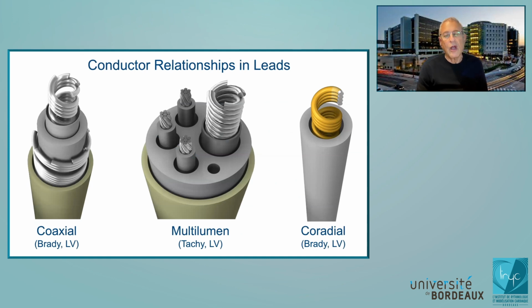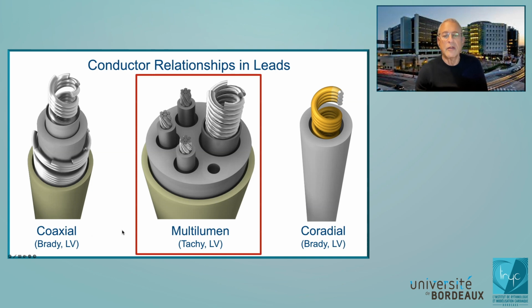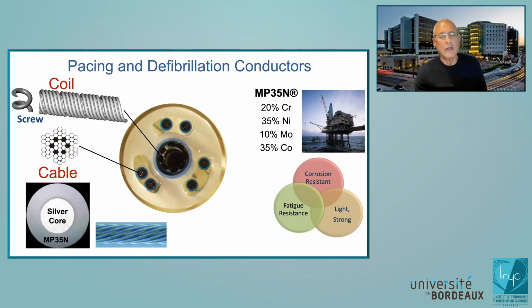Now, how are the plastic and the metal arranged? There are a number of possible arrangements used in various pacing and defibrillator leads. Presently, all implantable defibrillator leads are what we call multi-lumen leads, meaning there's a big block of silicone plastic drilled with a bunch of holes, and through it, metal runs. There are two types of metal conductors. There are cables and there are coils. Why do we have a coil on the lead? We have a coil on the lead because this coil can be used to extend the screw at the tip to fix the lead to the heart.